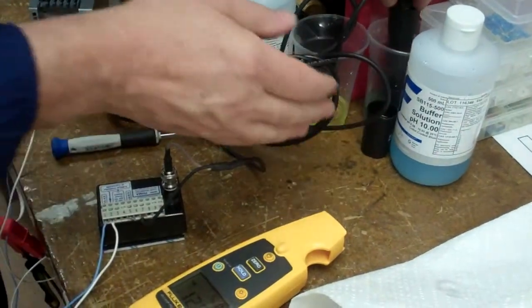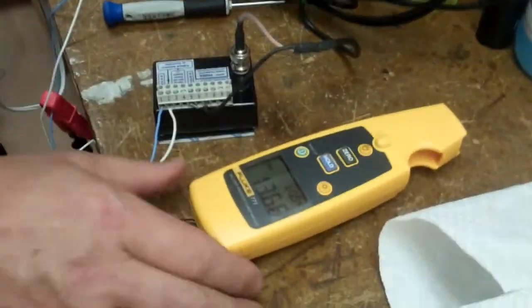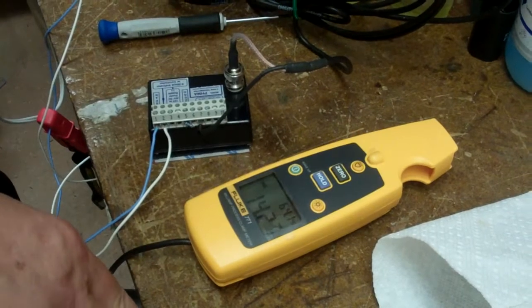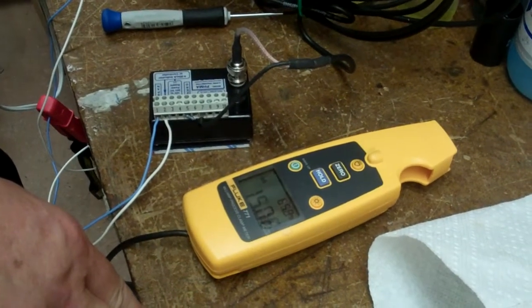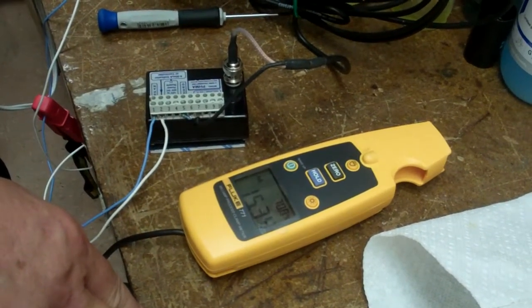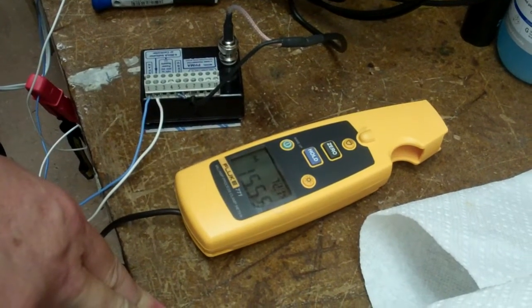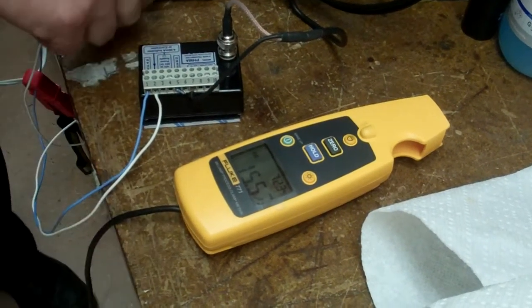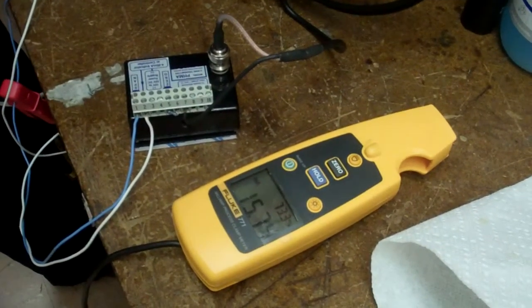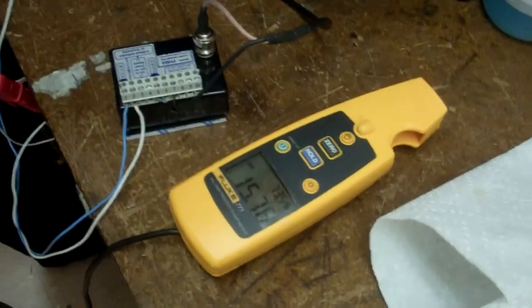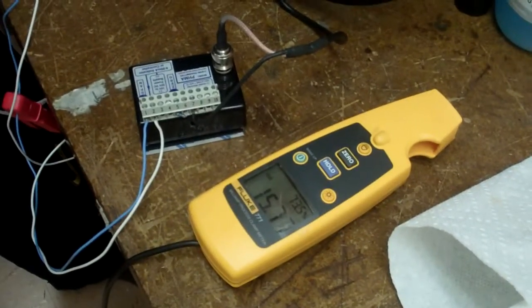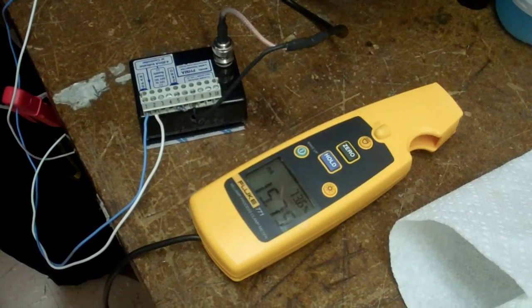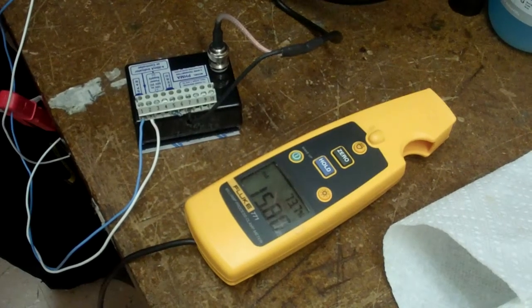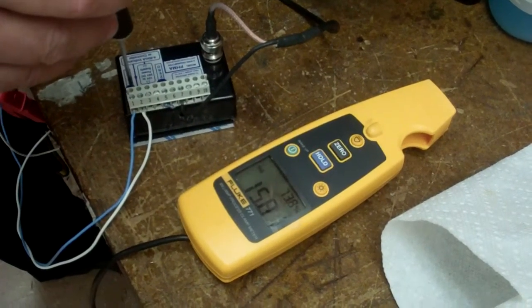Dry off the end of the probe. Put it in my other solution. This is going to go up. It's going to go up above 15. I want 15.4 in, remember that. And this will be a span adjustment. .8 is where it went to. I'm close.